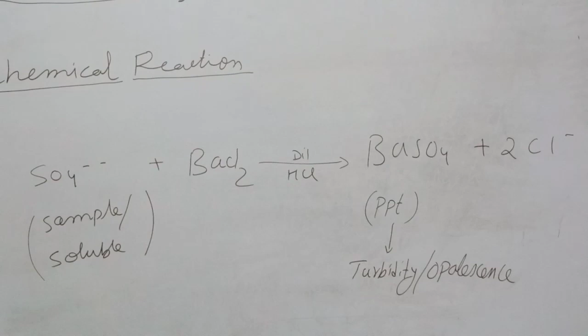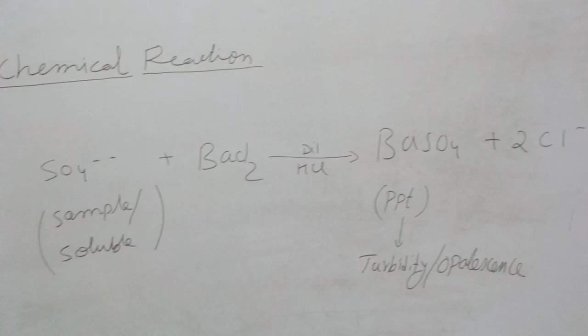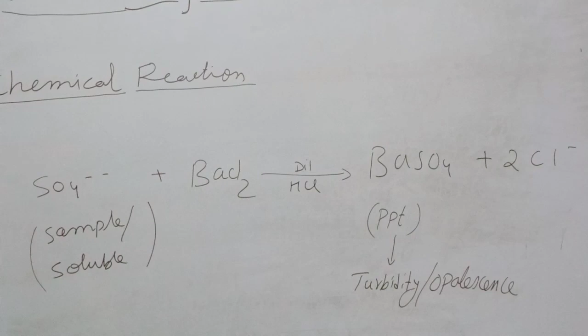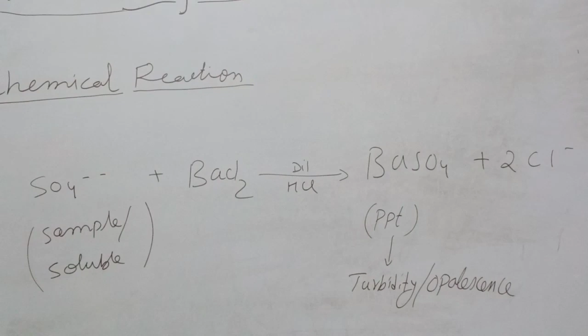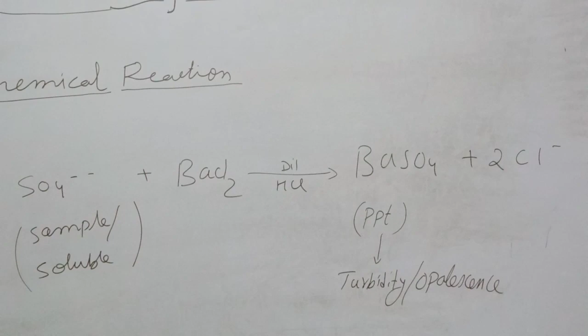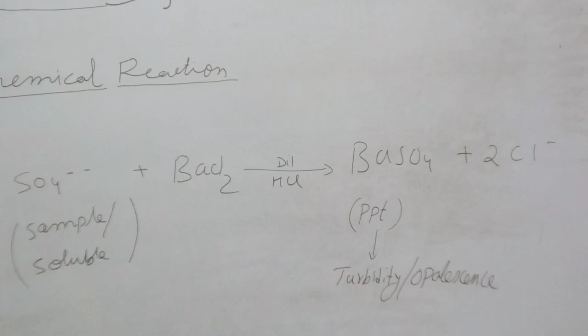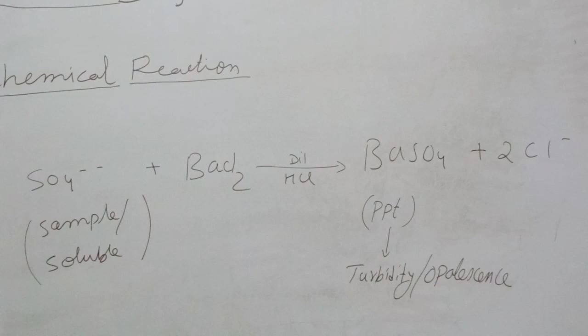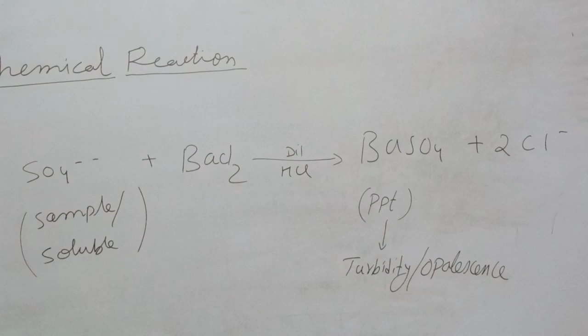So under acidic condition, this barium sulfate, which is yielded by reaction between sulfate and barium chloride, gets precipitated out from the solution due to dilute hydrochloric acid or the acidic condition, and once it gets precipitated out, it causes turbidity or opalescence. And this turbidity or opalescence, produced by the precipitation of barium sulfate, is directly proportional to the net quantity of sulfate present in the sample. In order to determine the degree or extent of sulfate present in the sample, we compare this turbidity or opalescence produced by the test sample with a standard or reference compound which has a known quantity of sulfate. By comparing the turbidity or opalescence of test with reference, we can know whether the sulfate present in our sample is within the limit or out of the limit.